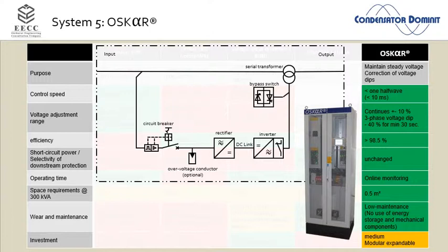Then we had another challenge when we were developing the system, and that is a bypass. The worst thing that can happen to a serial system is if my customer has a short circuit on his side. For whatever reason, again, some idiot is jumping into the switchgear, a motor has a broken isolation, whatever. In that case, I want to have my short circuit current fully available, because my blowing fuse is my safety. My circuit breaker must trip by any means. That means my short circuit current must be as fast and as big as possible.